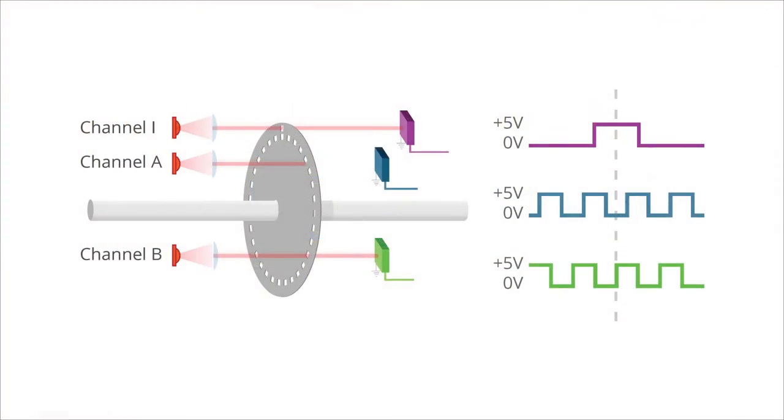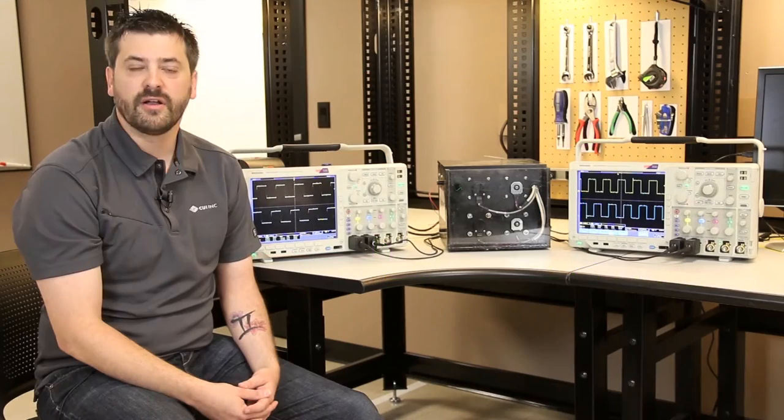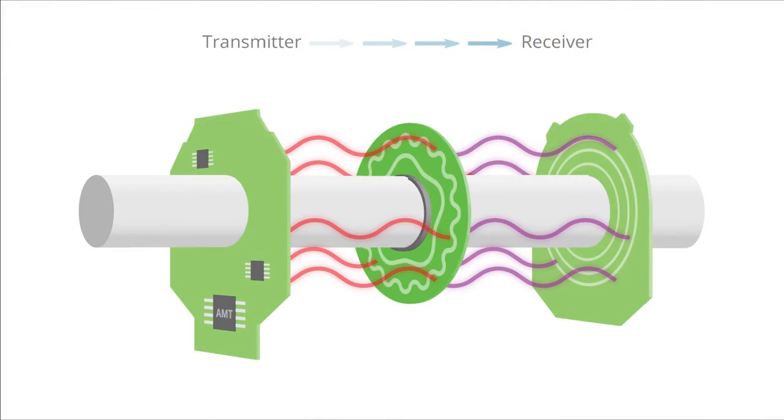Optical encoders require line of sight, and if it's a dirty or dusty environment or a lot of oil in there, that can drastically influence the performance of that optical encoder. An AMT encoder, being capacitive-based, is not susceptible to airborne contaminants or any oil in the system, making it ideal for a lot of motion control applications.